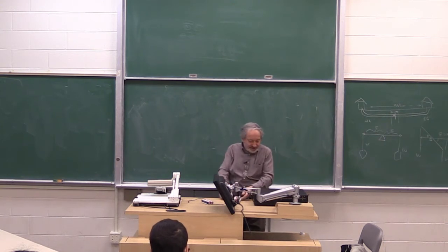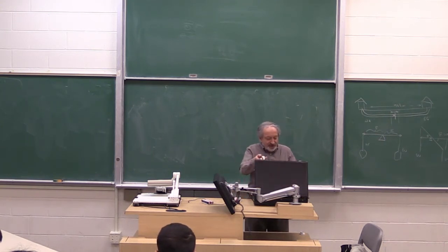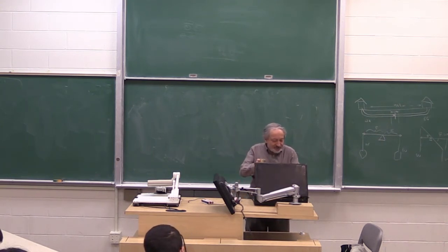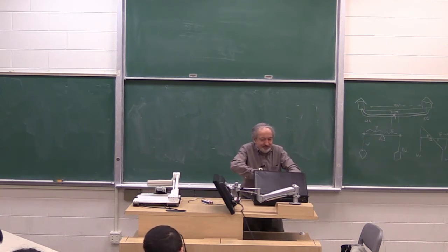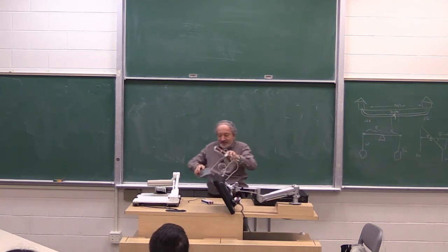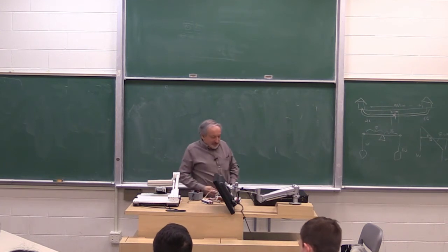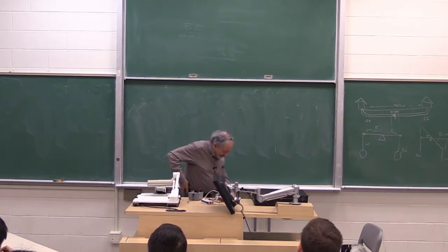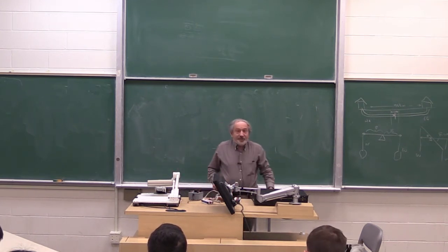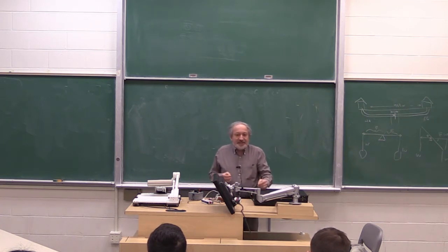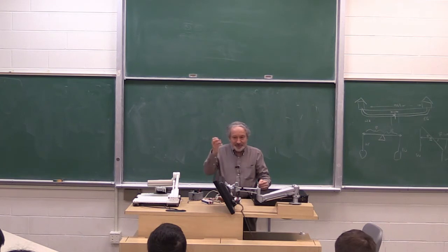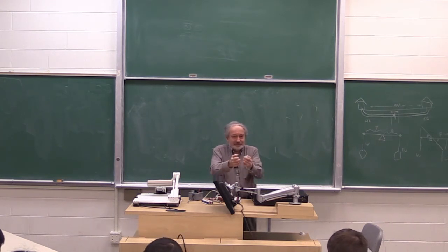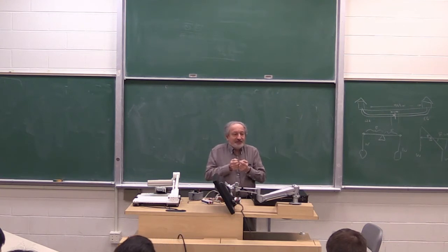So let's talk about modern sensors. The most common sensors are sensors to measure displacement. The reason these are the most common is that from displacement you can derive other things. For example, if you want to know acceleration, you put a mass on a spring. When you accelerate, the mass deflects the spring, and if you measure the displacement, you know the acceleration.